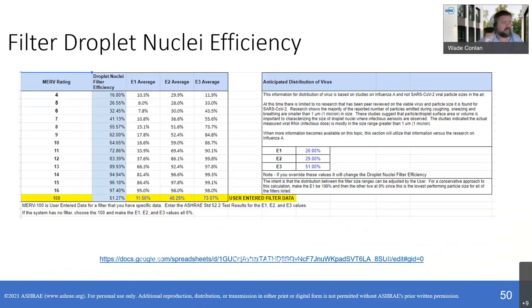So make the E1 zero. That's the lowest performer for filters. The table on the left is the MERV rating, 4 to 16. There is no MERV 17. HEPAs are tested to a different standard, so you can't have that. But we took over 200 filters of existing filter 52.2 performance data and then summarized it within its MERV rating to say, okay, here's how well they're actually doing. And you take the E1 average of the filter times how much virus percent you think will be in there, E2 times E2, et cetera, and then you can get your droplet nuclei filter efficiency.